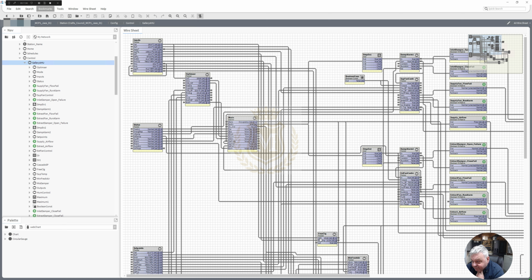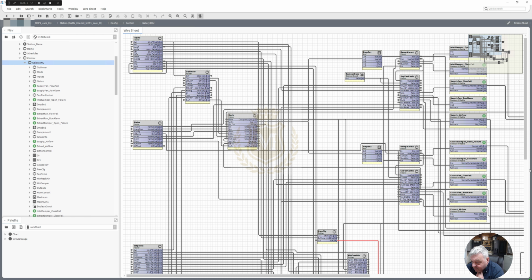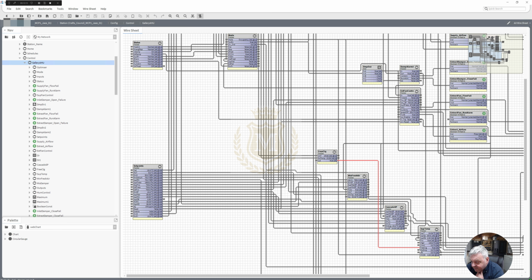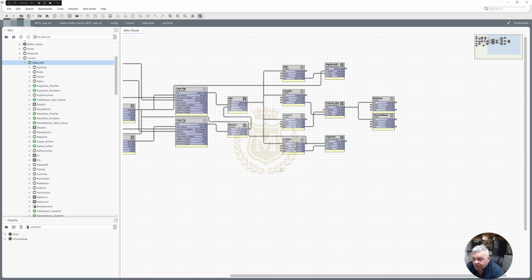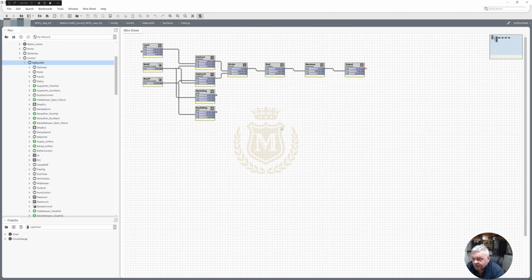And if we go back into the free cooling, we've got outside air at 25.92 and external at 23.3. So we do have a difference between it, and that is actually true. So we will follow that through into this free cooling here. True. So there's our switch. We're in true. So it would take it from there. Now our out at the moment is 0, because we are actually using the heating loop at this moment in time to maintain the temperature. But if we weren't using the heating loop and we were using the cooling, then that would be different.